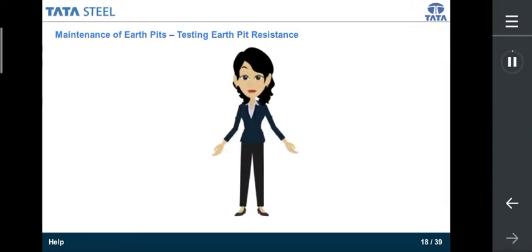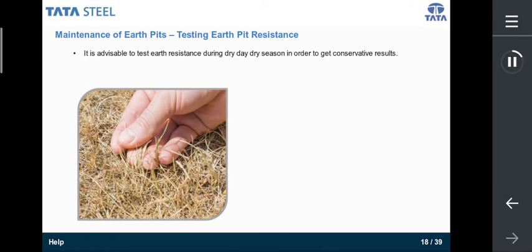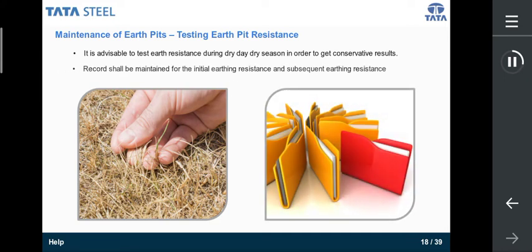Once voltage is checked across the earth electrode and earthing lead and is found to be below 5 volts, testing is done. The next step is to test the resistance of the earthing pit. It is advisable to test earth resistance during a dry day, dry season, in order to get conservative results. Further, records shall be maintained for the initial earthing resistance and subsequent earthing resistance.